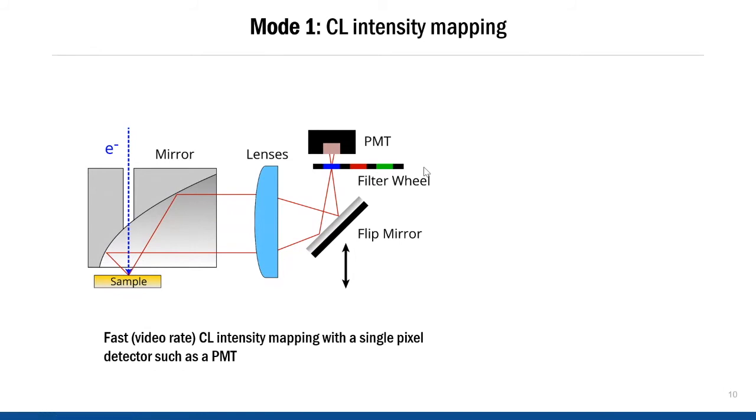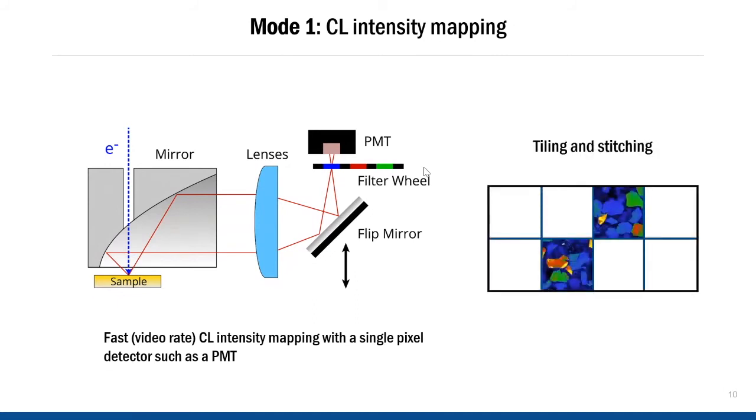The advantage of this mode is that it can be very fast. It's possible to use dwell times shorter than 10 microseconds per pixel, so you can do video rate imaging, have a live scan, and you can scan the sample very fast and decide what you would like to image in more detail because that's not always clear from the beginning. Another important feature of this mode is that you can scan a large field of view. With the electron beam, you can scan half a millimeter by half a millimeter, for example. And then by scanning the stage, you could build up an even larger image tile by tile. This is particularly nice for geological samples where the features can be quite large. You can image tiles in an automated manner and stitch them and have a very large area image.